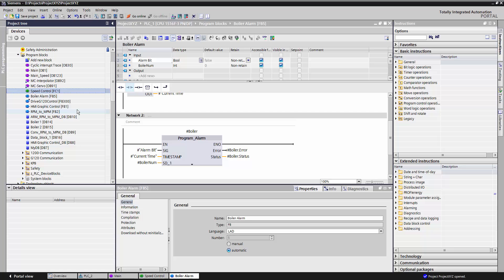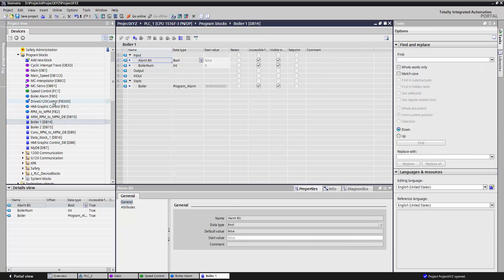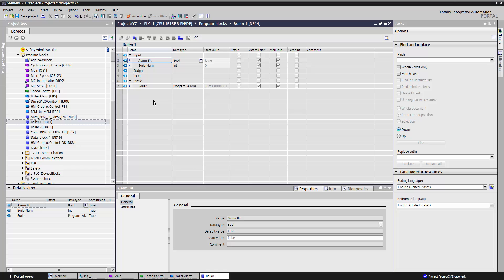So in order to record the average temperature from one motor to the next motor, that data has to be retained individually. And that data is retained in what's called a data block, as indicated by the blue cylinder. A data block is basically a container of data. When it is used in conjunction with a function block, it is known as an instance data block. And that can be shown here, it has an input field, output field, and for the variables used in the middle of the function block, they're known as static variables.